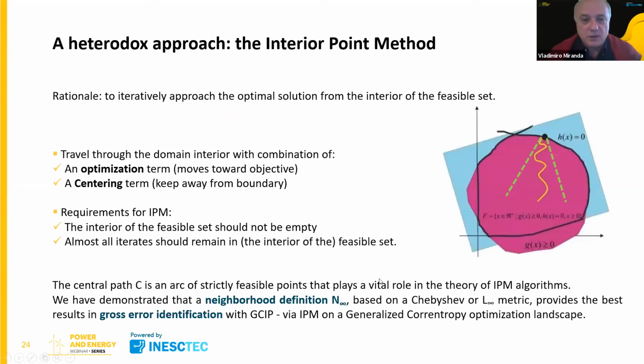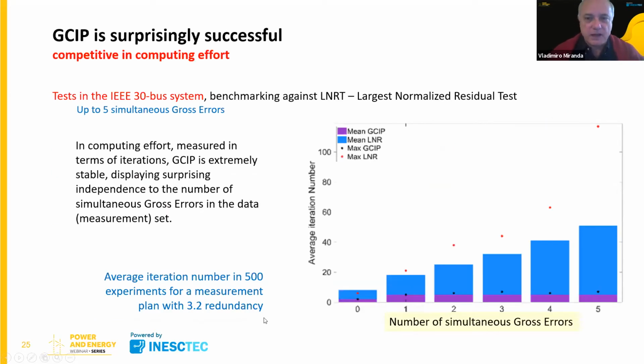And then we use the interior point method that is based on a central path concept, not approaching the boundaries of the problem. We proved also mathematically that using a neighborhood definition based on the Chebyshev metric, L infinity, we have the best results for gross error identification when we combine an interior point method with an objective function that uses generalized correntropy. Now, to convince you of this advancement, I'm showing you some results. In the competition between the GCIP method, the new method, and the old method called the largest normalized residual test, used to correct bad data in traditional systems, first processed with weighted least squares.